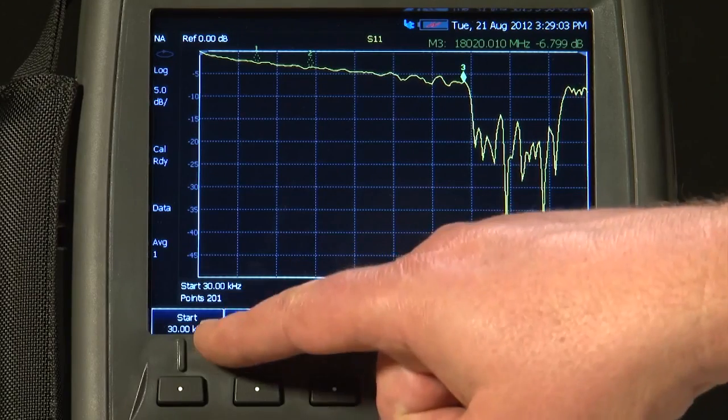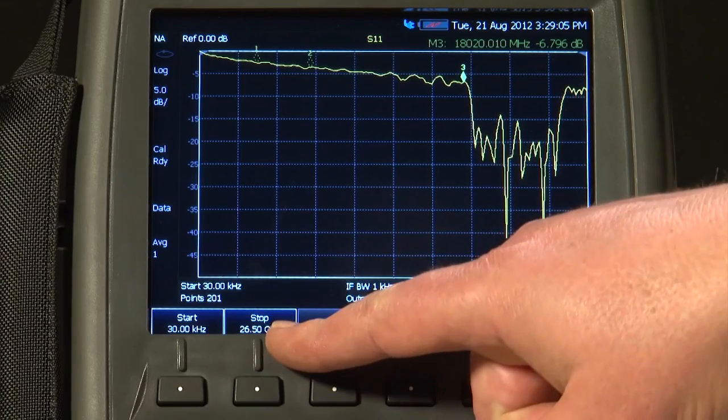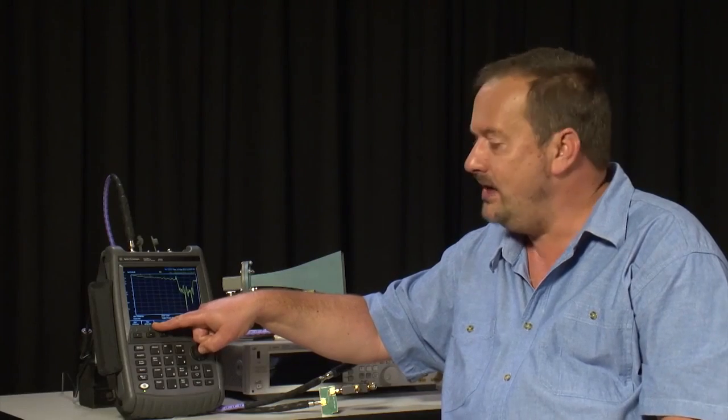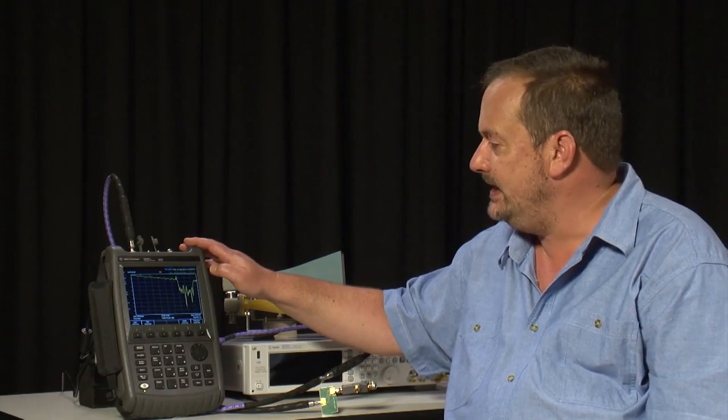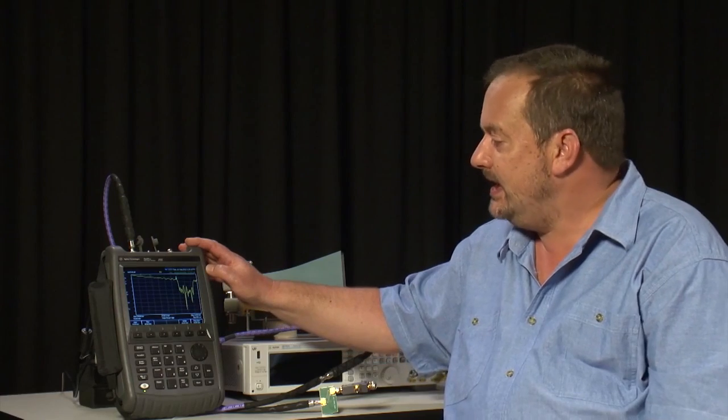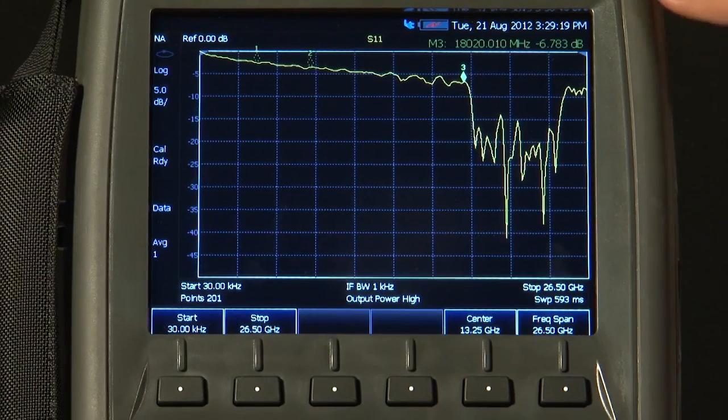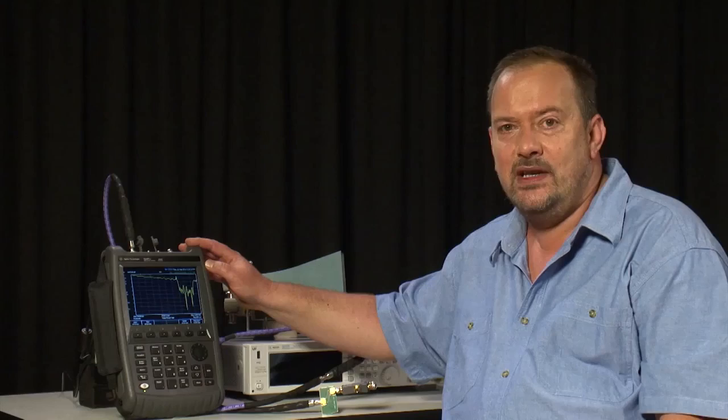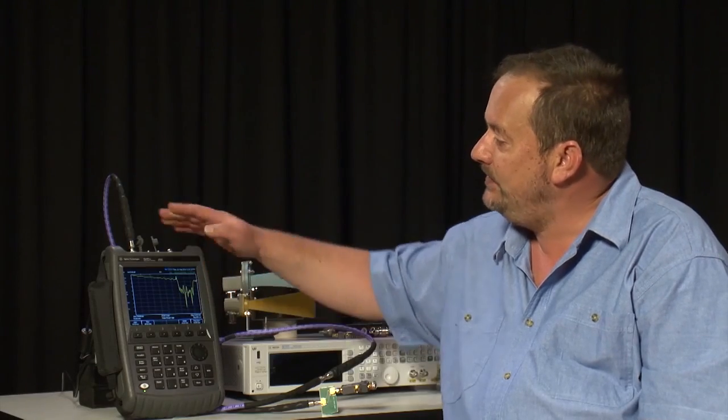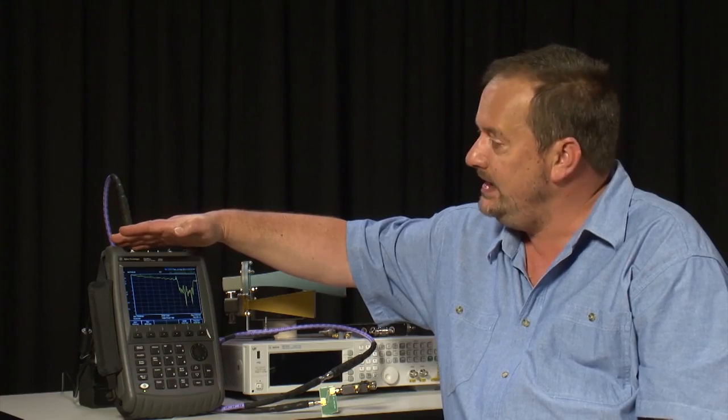You'll see I have set the frequency range on the FieldFox to cover its entire range. That is 26.5 GHz in the case of this model I have here. And in fact, I've just done an instrument preset. I'm not even going to perform a calibration because every FieldFox is supplied with a CalReady calibration where at the factory a full S-parameter calibration has been performed at the reference plane of port 1 here.